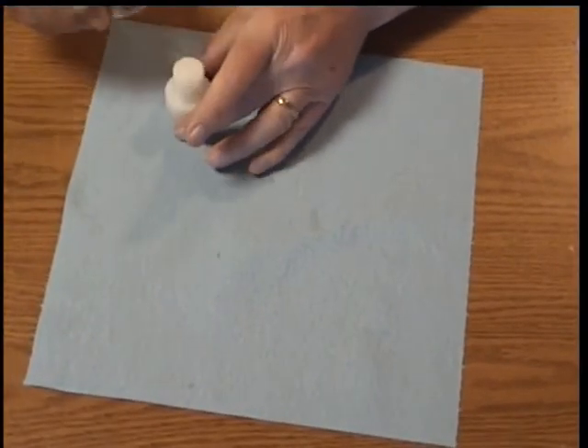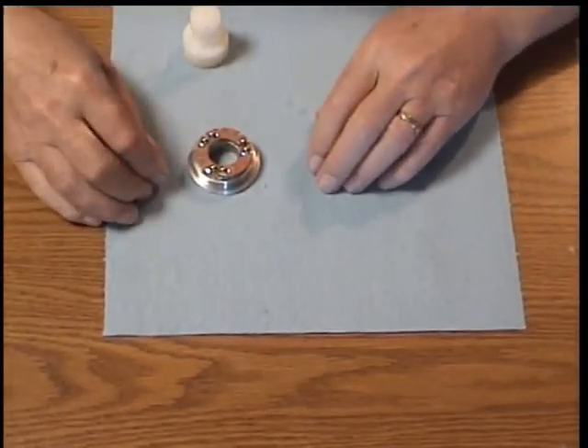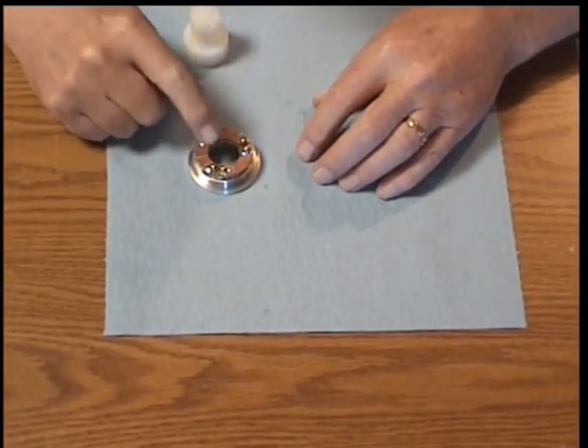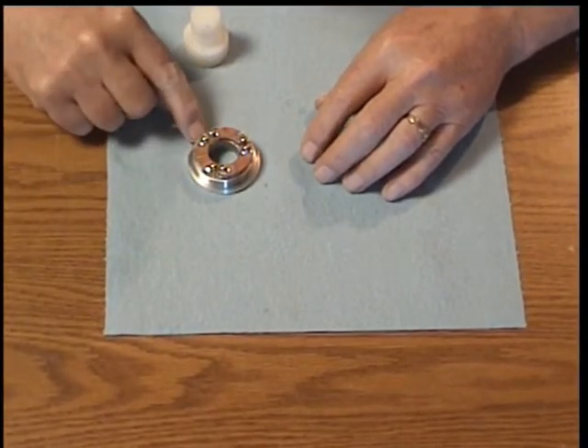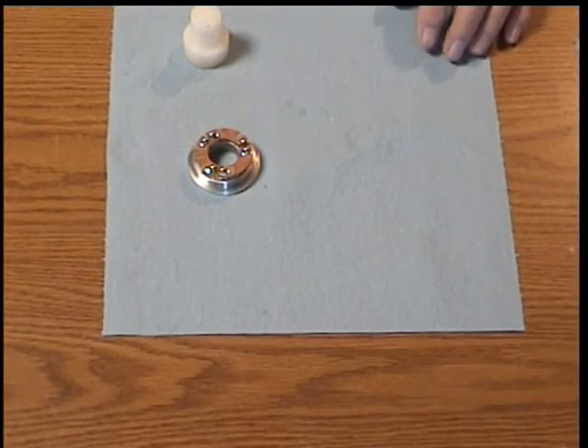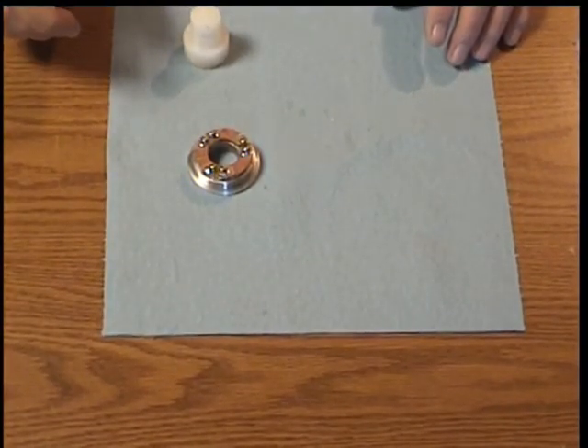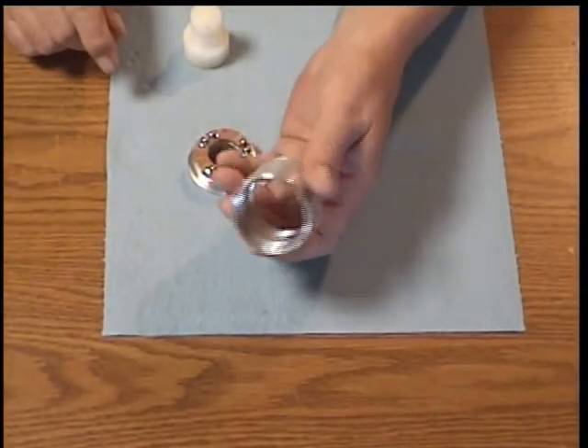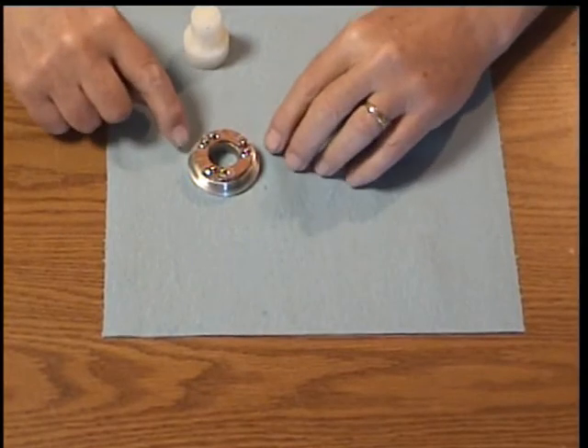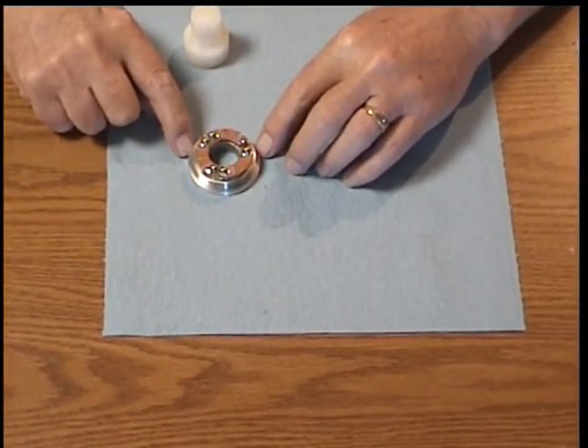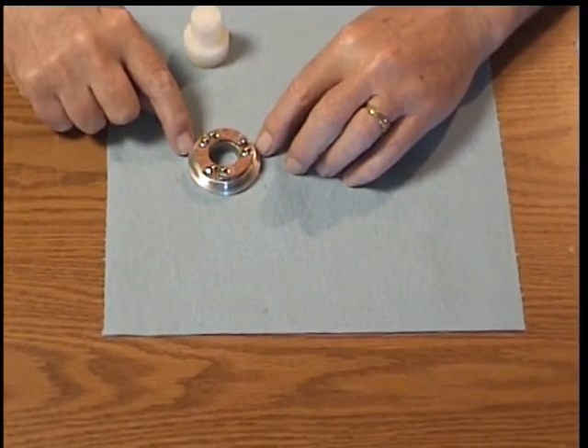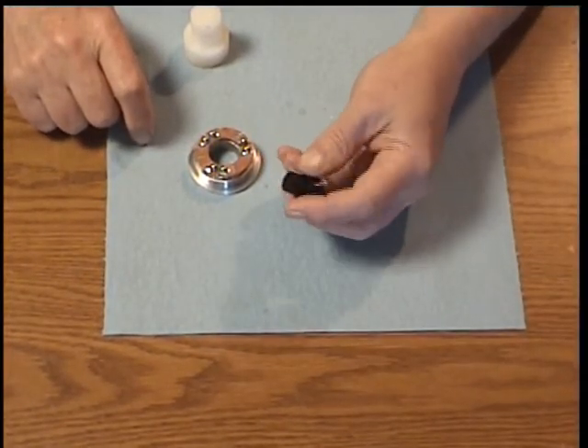Okay, take this apart. Now, if you would have done this by hand, you would have just had to sight down through this bore and line up these two openings. It doesn't matter if you're a little bit off because it's not the relationship of the printed circuit board to the body of the probe or even the printed circuit board to the bottom cap. There's quite a bit of tolerance in the relationship to those pieces. It's the relationship of the printed circuit board to the contactor and the adjustments that we make to that that we'll see later on that are important.